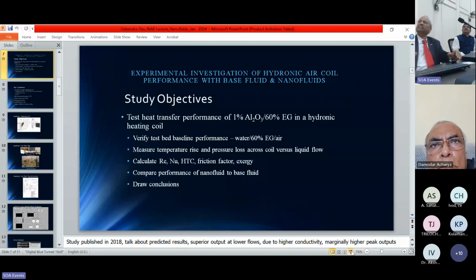We began testing the pure liquids used nowadays. In cold regions, we use 60% ethylene glycol or 60% propylene glycol in heating, because temperatures go below 0 degrees Celsius and water would freeze. In warm climates like Texas or Oklahoma, we use water for heating, but in northern climates like Minnesota, Massachusetts, Vermont, Alaska, and all over Canada, we use ethylene glycol.